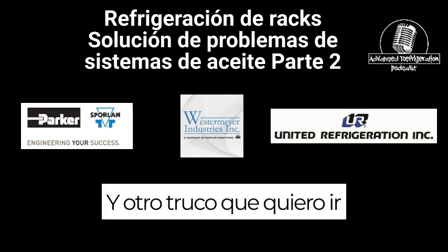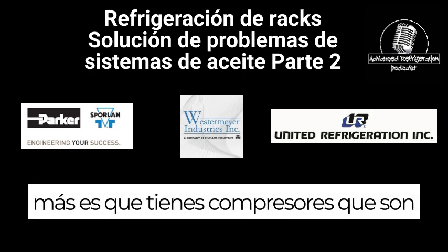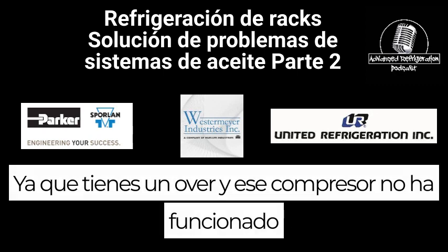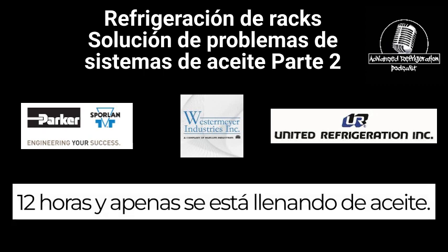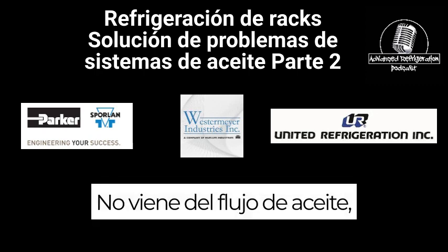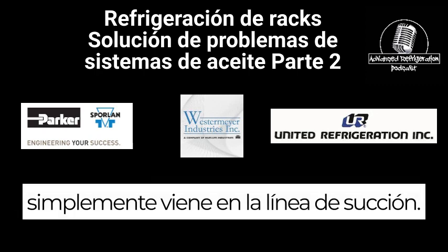One other trick I want to go over is when you have compressors that are filling with oil and they're not running. Say you have an oversized rack and that compressor hasn't run in 12 hours and it's just filling up with oil. It's coming down the suction line. It's not coming from the oil flow. It's just coming on the suction line.